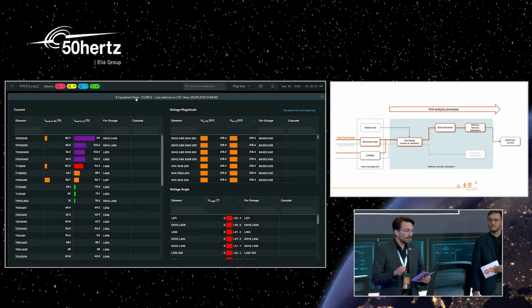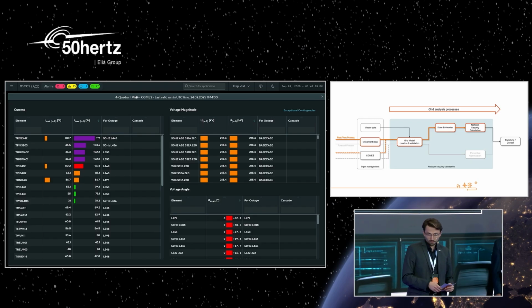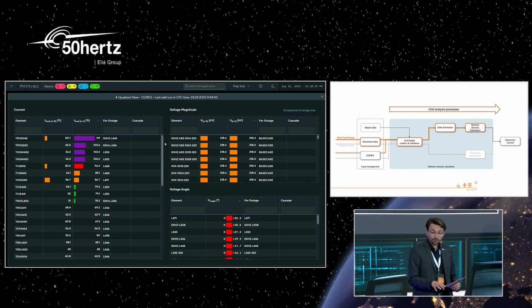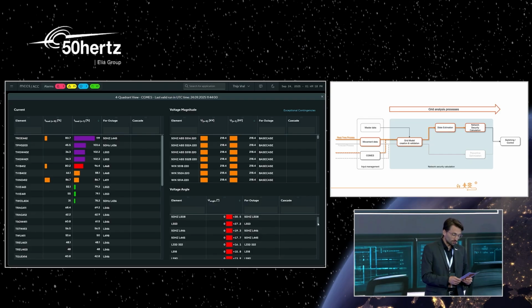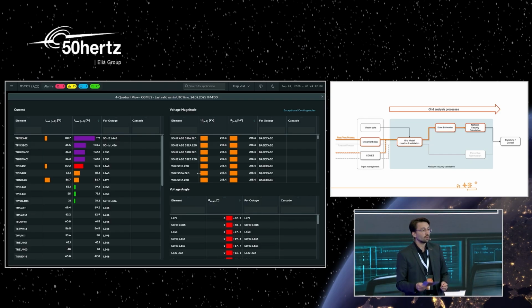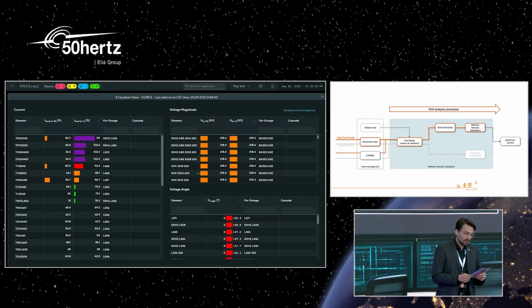This screen offers a direct and intuitive summary of the contingency analysis results. On the left side and the upper right side, we can see the currents and the voltages, in the base case on the left, and on the right side with the largest deviation based on the contingency analysis results. On the lower right side, we can see the voltage angles, which indicate if we can safely resynchronize the components after their failure. Soon there will also be a fourth table showing the results of cascading failures, helping us understand and anticipate possible chain reactions. This compact overview helps our operators quickly assess grid stability and react to possible N-1 violations in real time.